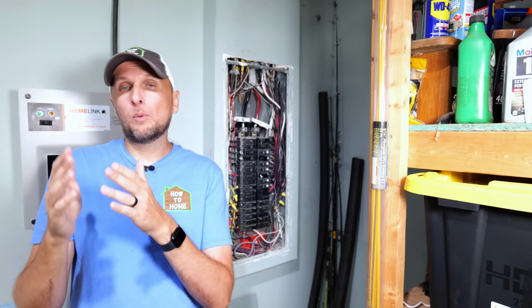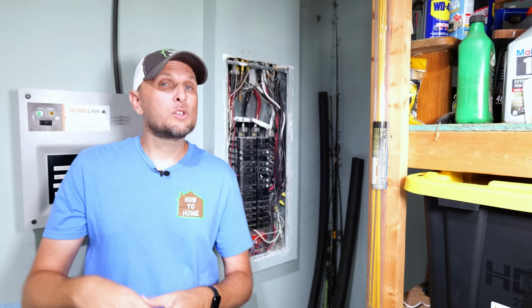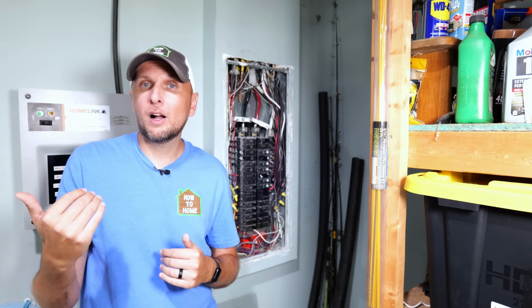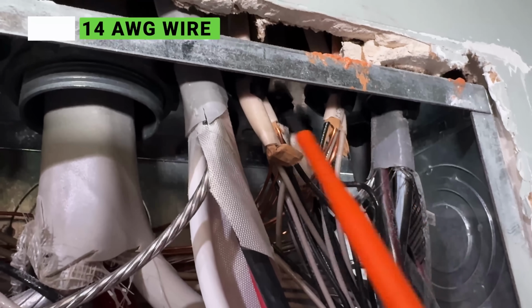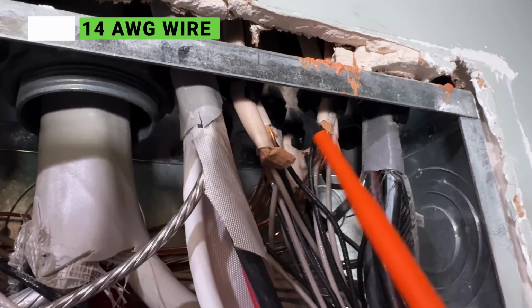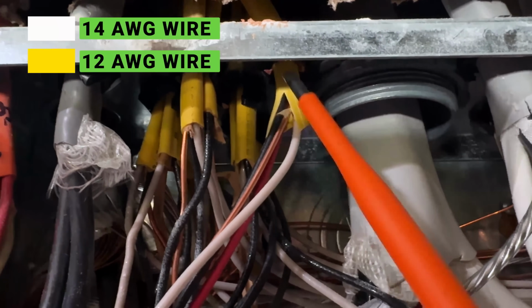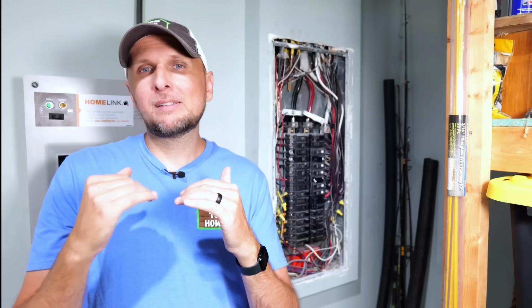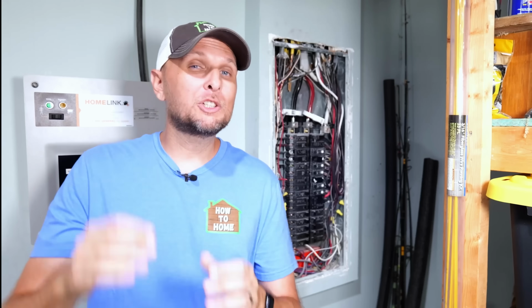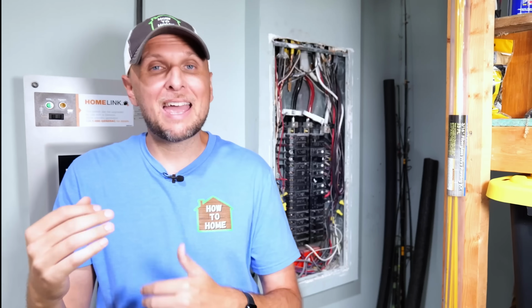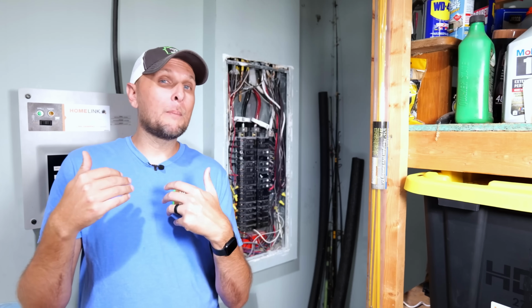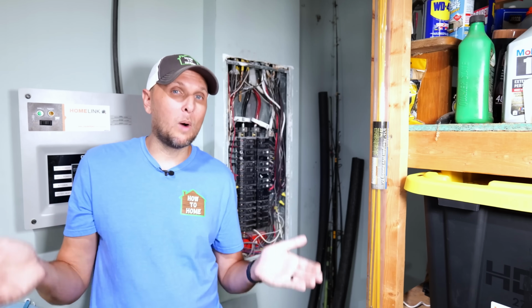And oftentimes, one thing that helps make this a little bit easier is Romex sheathing comes in different colors. And usually the white sheath Romex is 14 gauge and the yellow is your 12 gauge wire. So I can't stress this enough, how important this is to make sure that you're getting the wire size correct and matching it to that circuit breaker. Now, if you are thinking about using a different gauge wire, you can always go larger, but you can never go smaller.